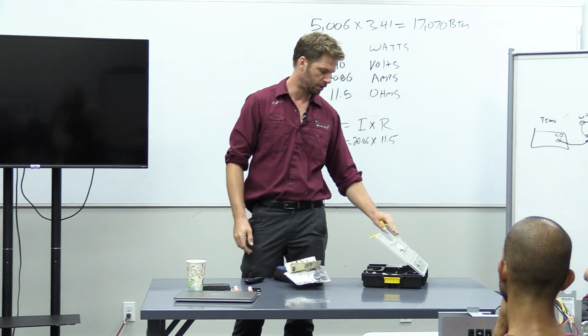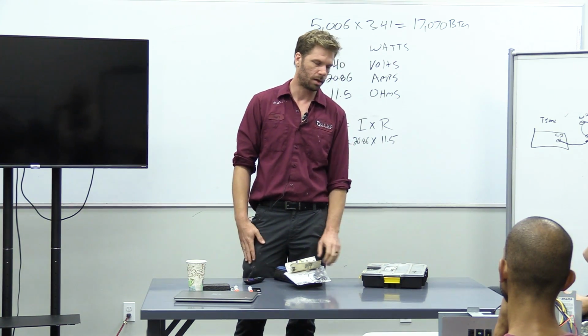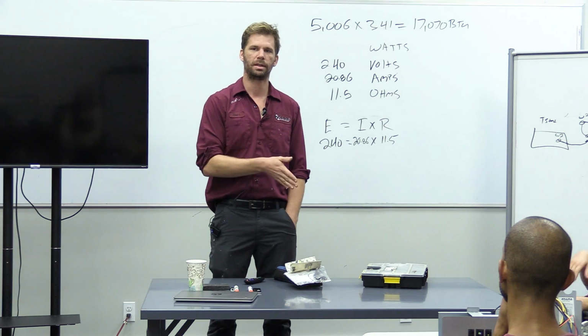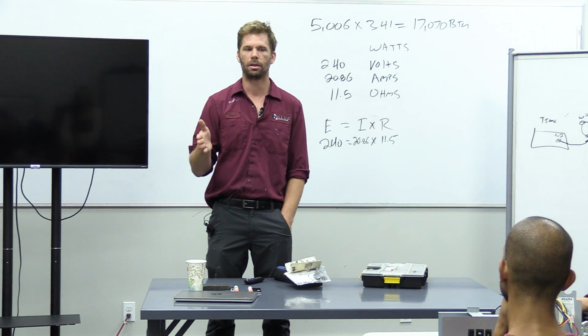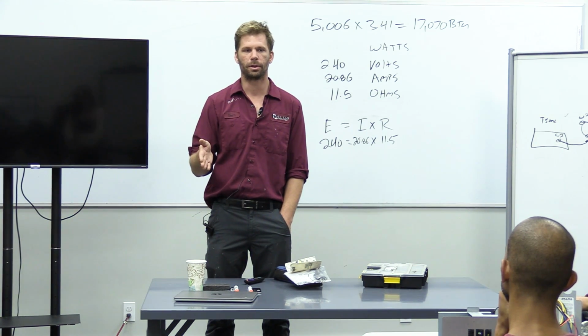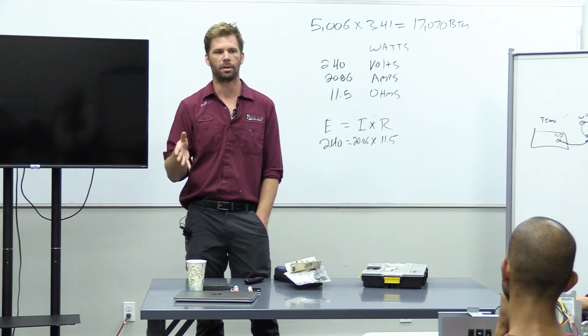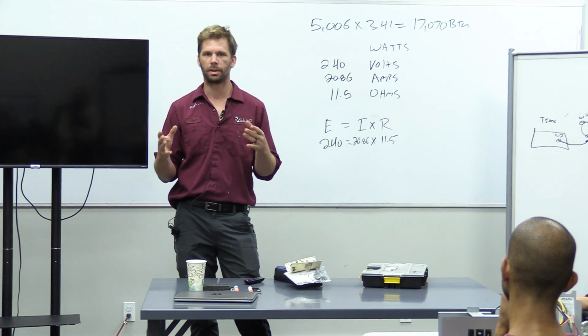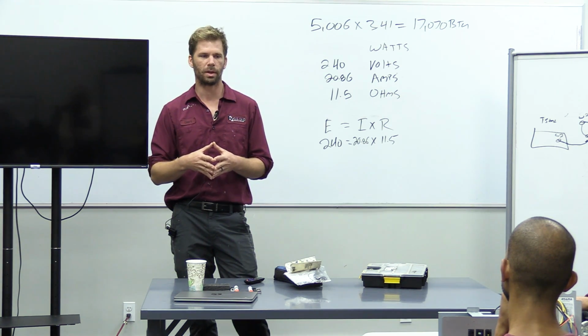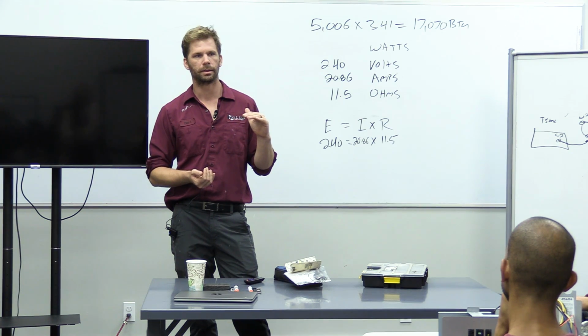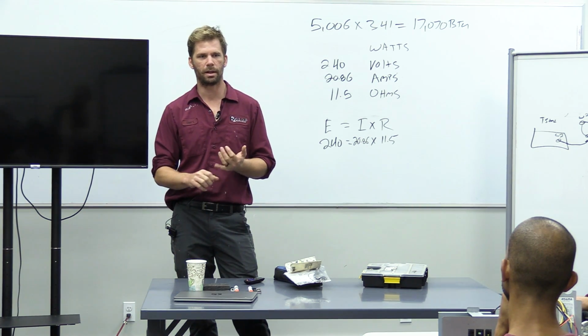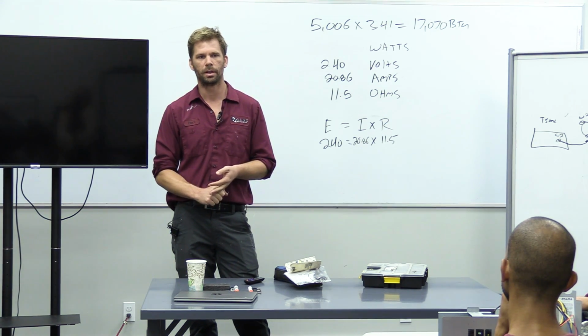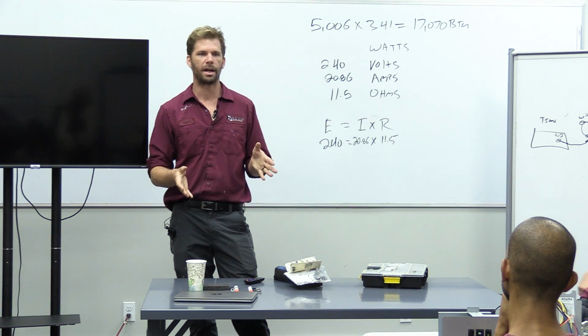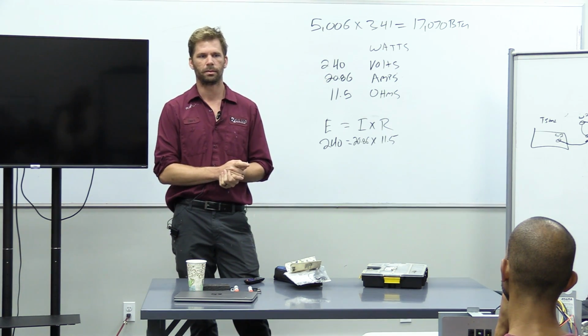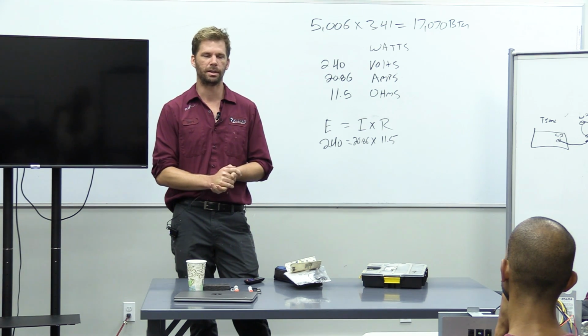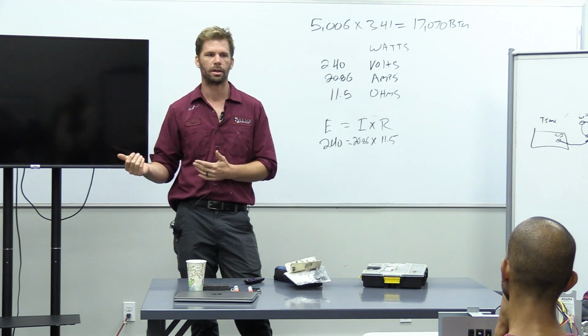Couple notes on high and low pressure issues. Because the water temperature changes so dramatically from maybe 60 degree pool to 102 spa, you're going to see a huge range in pressures. Don't just jump to adding refrigerant to pool heaters. Pool heaters can be pretty sensitive in charge. It's just a little bit smaller of a refrigerant circuit a lot of times, not all pool heaters, but some of them are smaller. And so you find really high pressure, try to figure out why. Is my pool hot? And is my incoming water hot? And is it pretty hot outside? That's why I have a really high pressure. Do I have 400 PSI on my discharge line, but my pool temperature is 72? Then I'm probably overcharged. Now I need to quote the customer to remove the refrigerant and weigh it back in.